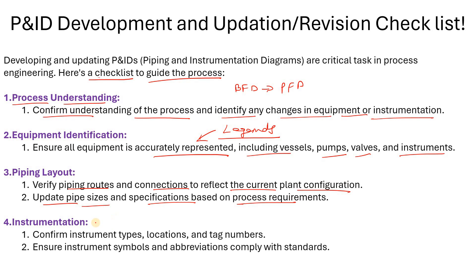The next point, which is very important, is your instrumentation. Confirm instrument types, location, and tag numbers. You will determine instrument types based on the fluid service, temperature, and process variables — which type of instrument is suitable. Then you will assign the tag number as per the area code or as per your P&ID. Ensure that the instrumentation symbols and abbreviations comply with standards — that point is also very important.